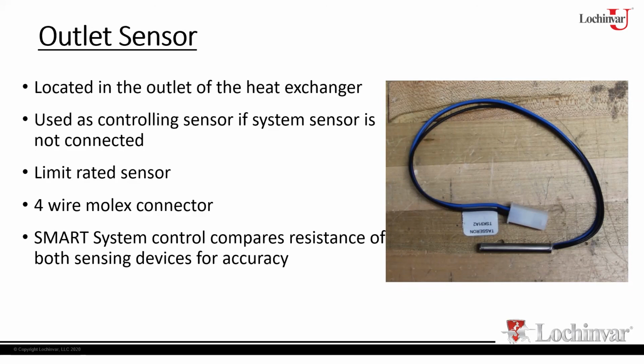So then you're going to go into a lockout. It's going to say lockout outlet temp differential. That means the temperature difference between the two sensors was too great. Generally, that just means it's a bad sensor. Now, it could be a wiring issue, so you do want to check the wiring, the plug, and make sure there's nothing disconnected there. But more often than not, it's typically a bad sensor, and you would just replace the sensor. So again, two thermistors within the body because it is a limit-rated sensor.